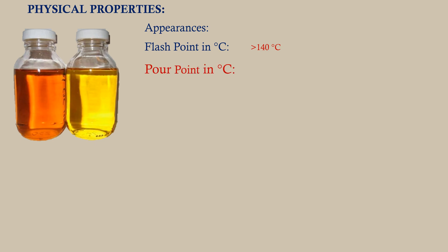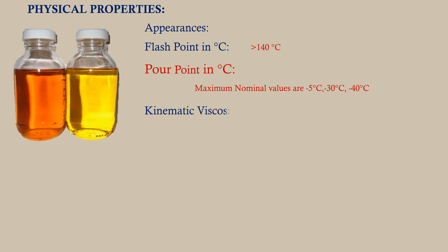Pour point in degree centigrade: the pour point is the temperature below which the transformer oil loses its ability to flow. Below the pour point, oil stops convection flow, and thus proper cooling may not occur.